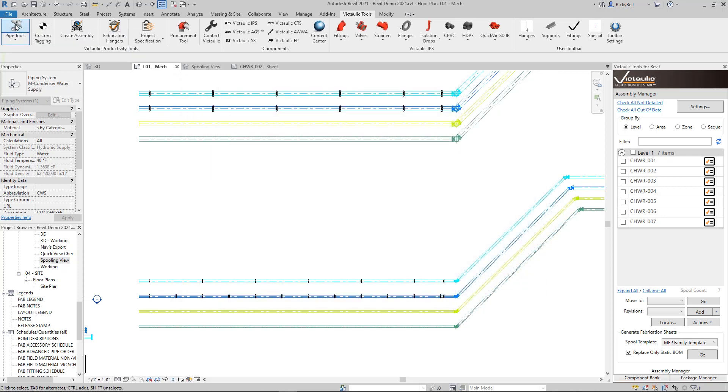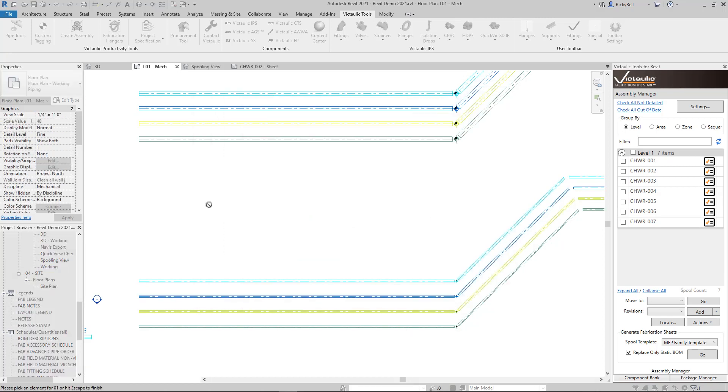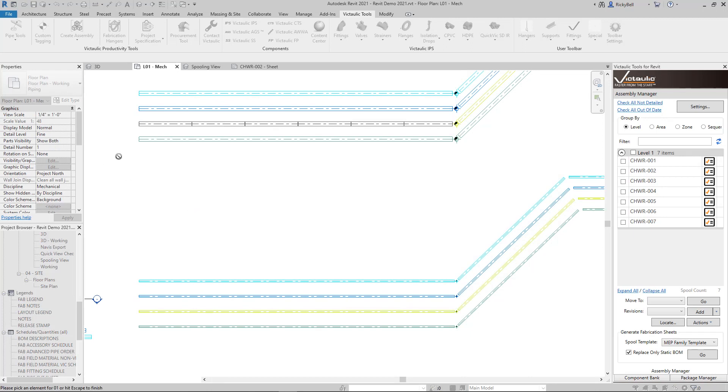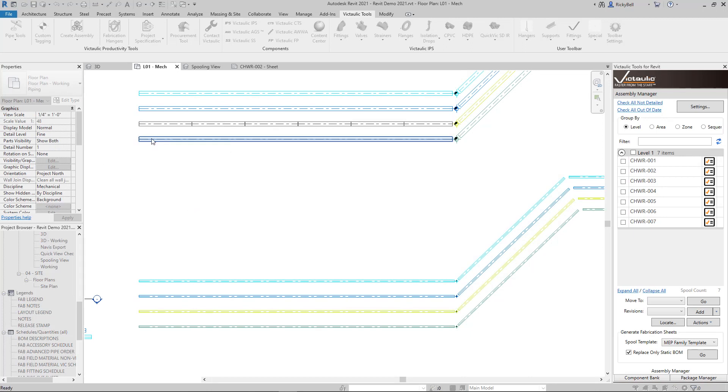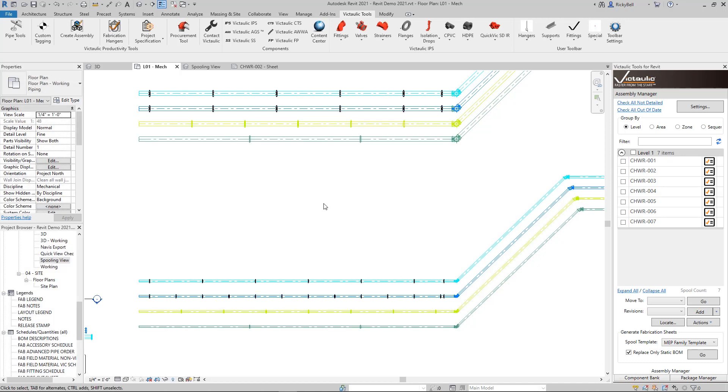When you go into our pipe tools dialog, you're going to see a very similar setup where you have the option to use the project spec, or you can use what's written here which is 1 foot minimum, 10 foot maximum. So using the project spec, splitting by length, other than that's default settings. I'll go ahead and hit the 10 inch return, 10 inch supply, 4 inch return, 4 inch supply. So as you can see you get vastly different results depending on the line within the project spec that it triggers.